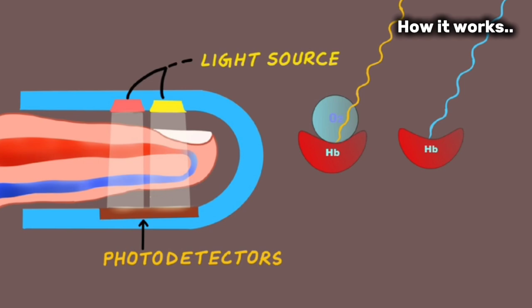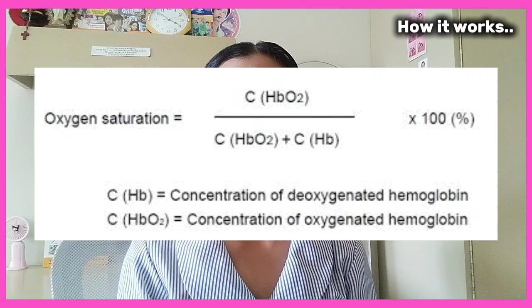We have talked earlier about the LED light source, right? It emits two different wavelengths. The first one is your red light, which is absorbed more by the deoxygenated hemoglobin. And we also have your infrared light, which is absorbed more by your oxygenated hemoglobin. Then, your photodetector on the other side measures how much of each wavelength of light is absorbed. And then, your microprocessor will calculate the ratio of absorbed red versus infrared light. So, the formula would look like this: R equals absorption of red light over absorption of infrared light.